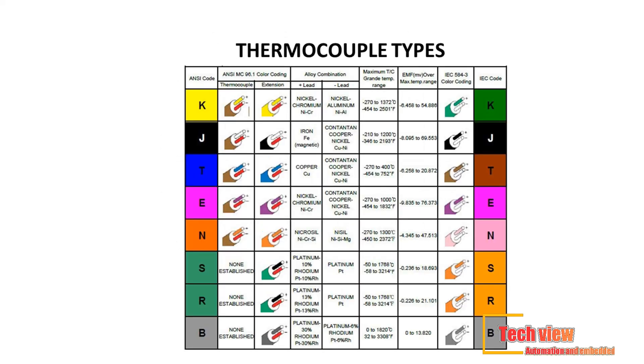Thermocouples are available in different combinations of metals or calibrations. The most common are the base metal thermocouples known as types J, K, T, E, and N. There are also high temperature calibrations, also known as noble metal thermocouples, types R, S, C, and B. Each calibration has a different temperature range and environment, although the maximum temperature varies with the diameter of the wire used. A very thin thermocouple may not reach the full temperature range.